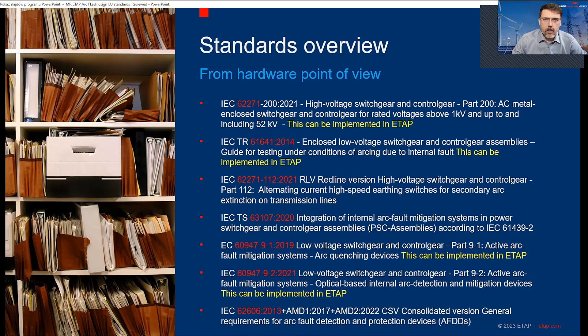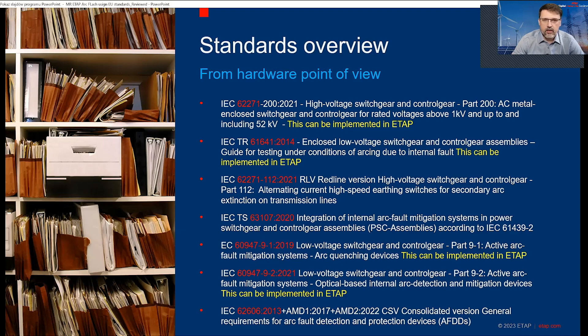From a hardware point of view, you might also look into IEC 62271, which is generally the standard about making high voltage switchgears. There is one part about internal arc classification — passive design for the switchgear. This can be implemented in ETAP. There is also technical report IEC 61641, which is the same topic but for low voltage assemblies — and you can also implement this as a check in ETAP.